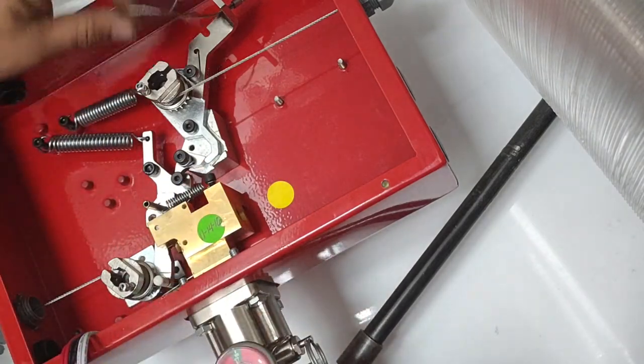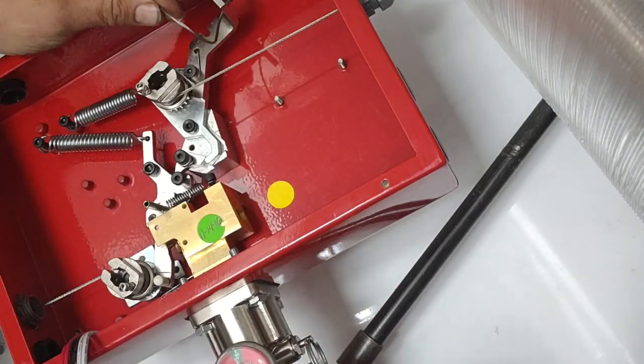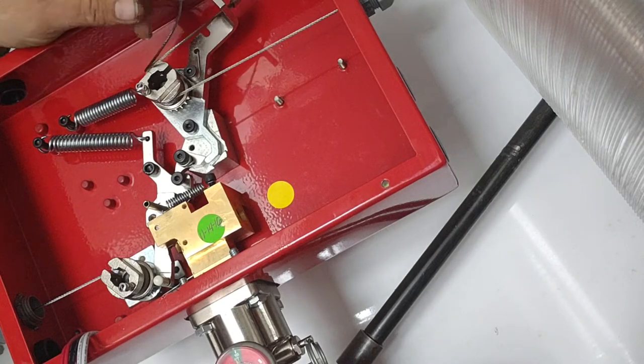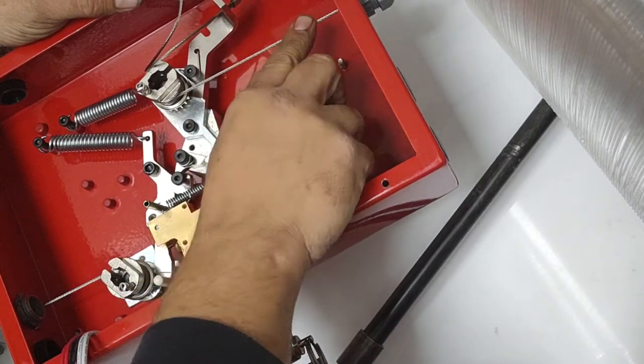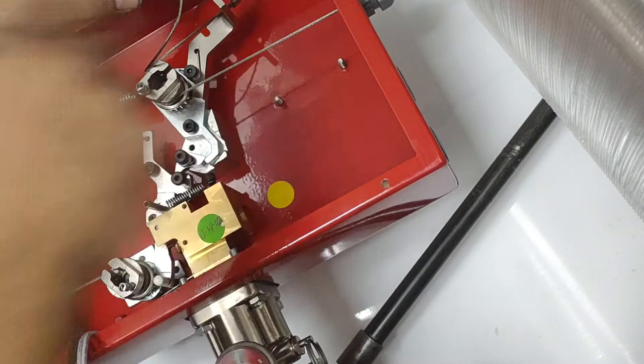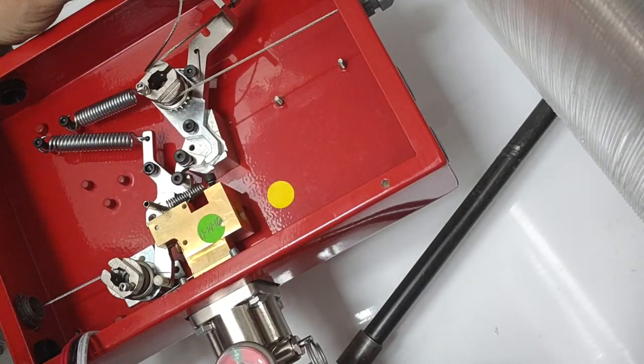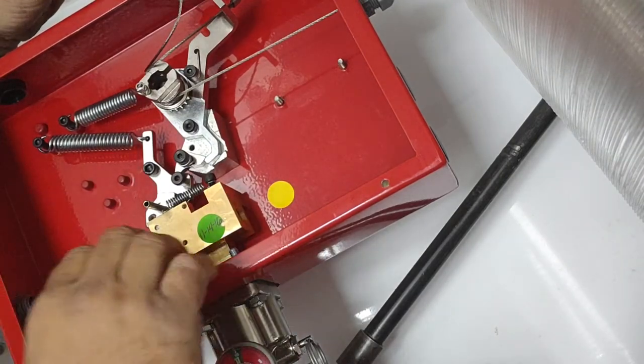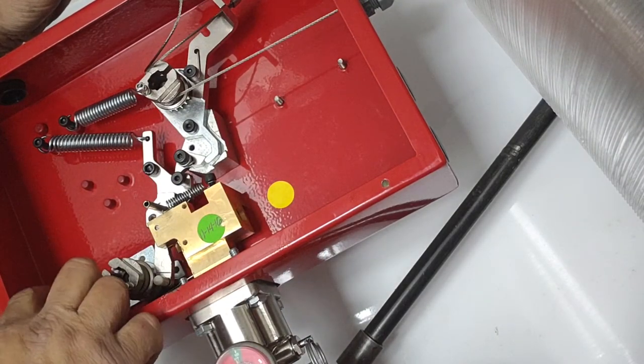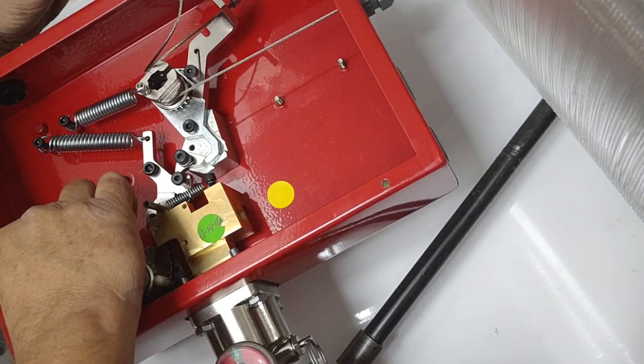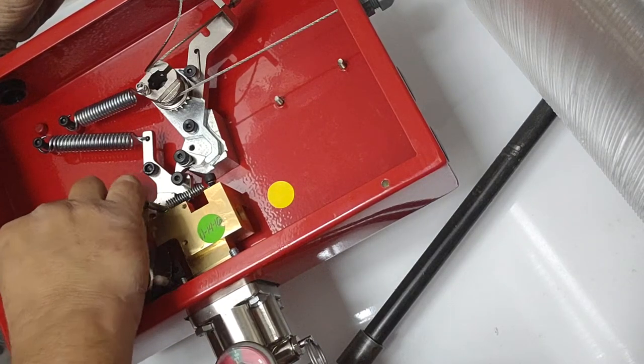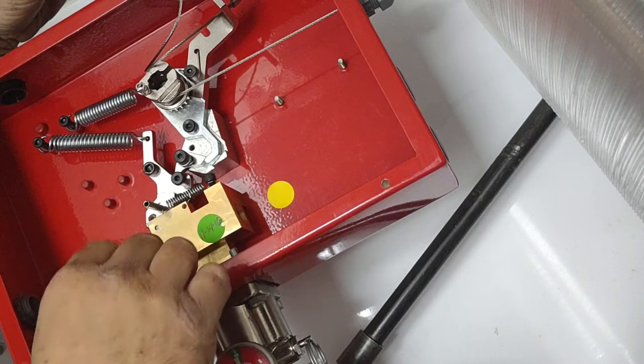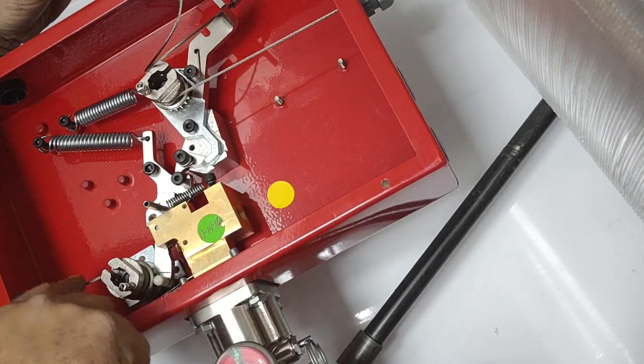This is how it's supposed to look when armed. This little wire right here goes to your manual pull station. This one here goes to your automatic detection, which has fusible links in your kitchen hood. And this is for your gas valve over here.